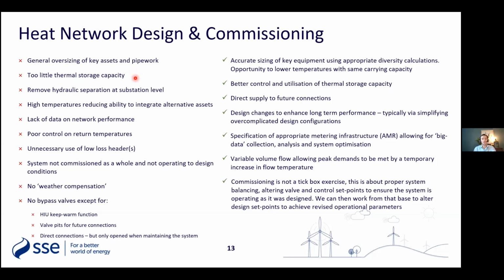And the problem when you oversize equipment is you end up with a whole range of issues, like short cycling of equipment, high return temperatures, so your heat pumps don't run effectively. You end up with pumps not meeting their minimum flow requirements. I worked on a network where that minimum flow requirement was causing such loud banging in pipe networks that they had to move around 300 residents out of an apartment block and put them into a hotel until it could be resolved. So please do not oversize equipment.